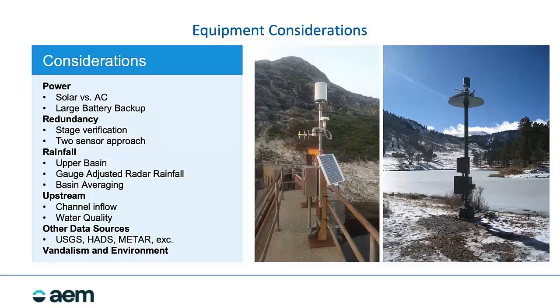Redundancy -- I kind of talked about stage. We typically don't want just a single stage sensor. Having another source, a radar, a bubbler, a float switch, we want that two-step verification. In that case, if a sensor were to fail, you still have that backup, or if both sensors are operational, you have that verification that what you're reading is real.